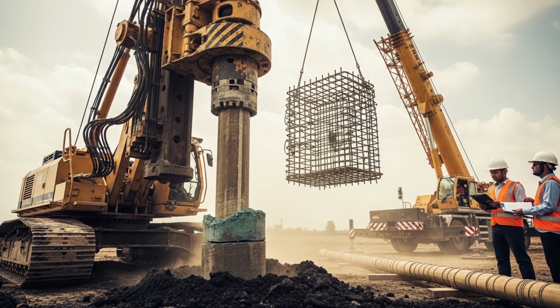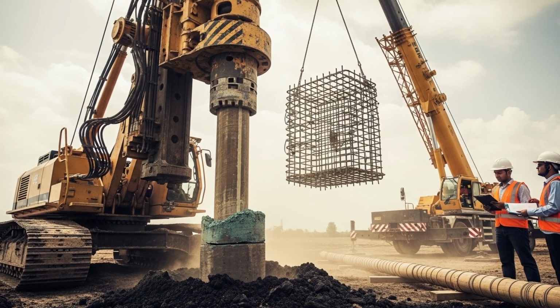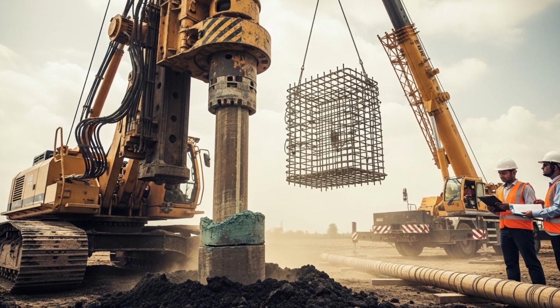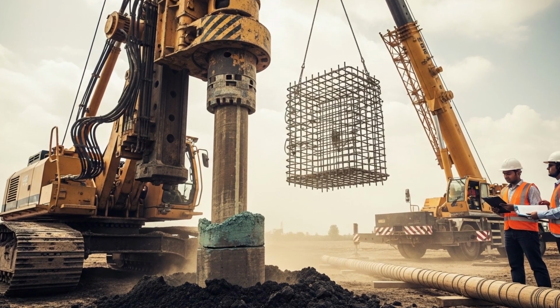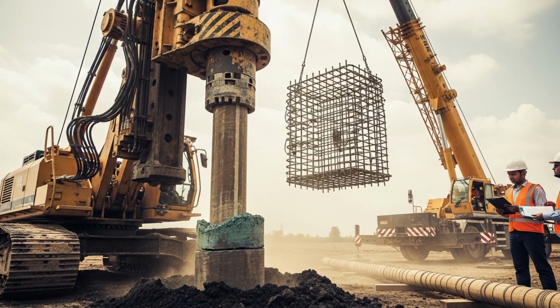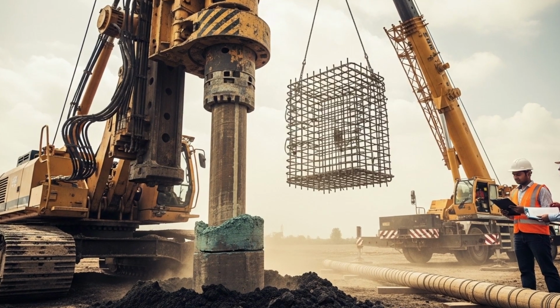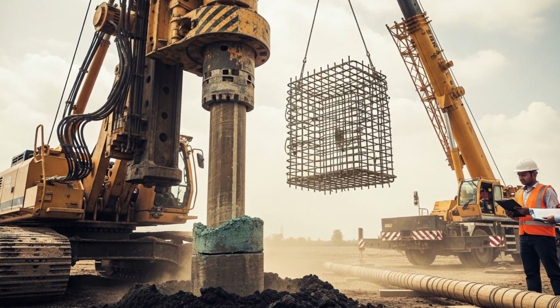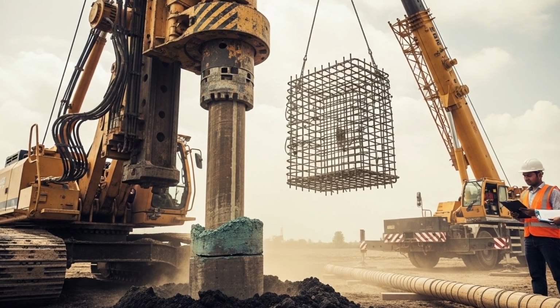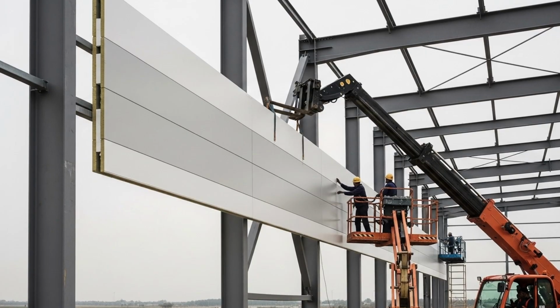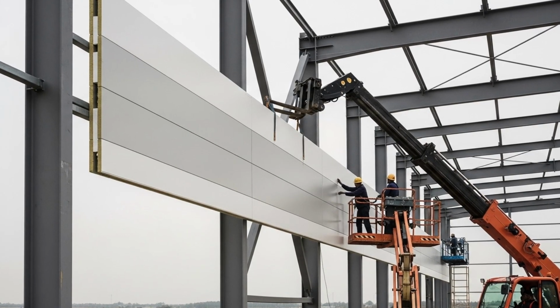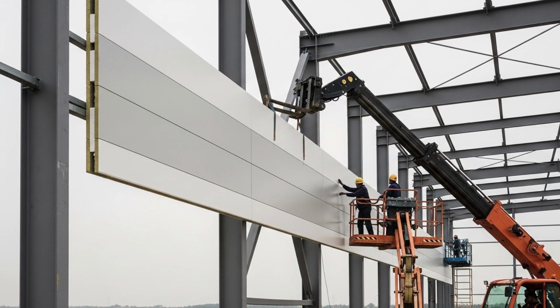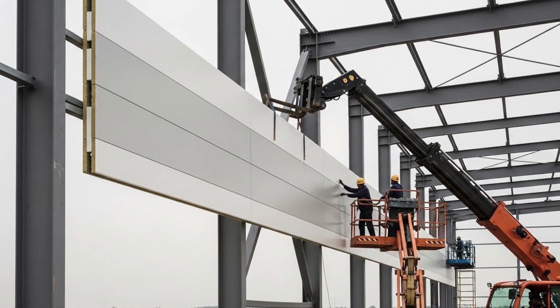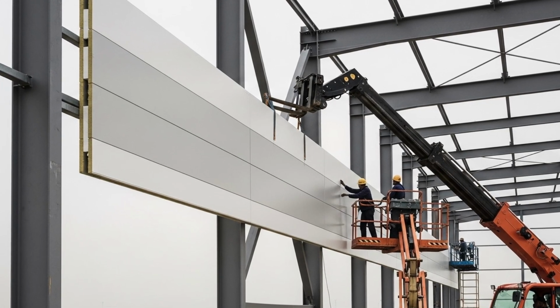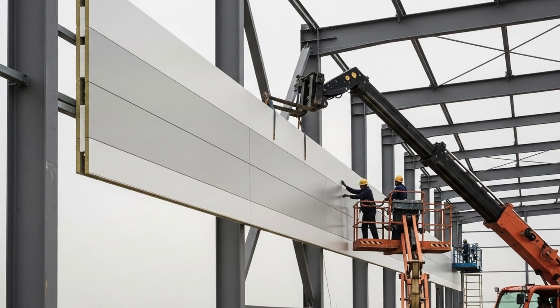So it has to be designed for heavy loads. Remember, the server halls have very high floor load requirements. Pile foundations or raft foundations are common depending on the soil conditions. The structure is typically RCC, that means reinforced cement concrete, or pre-engineered steel frame. Floor to floor height is kept high in these buildings, up to 6 to 8 meters, to accommodate large MEP services running overhead.